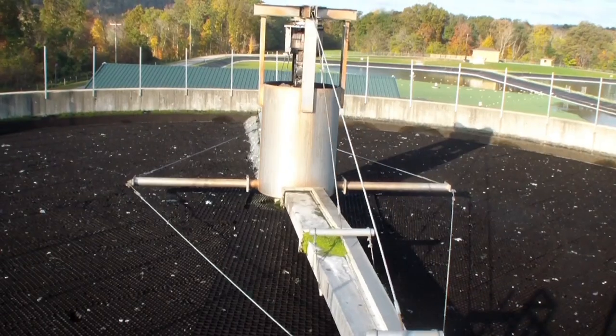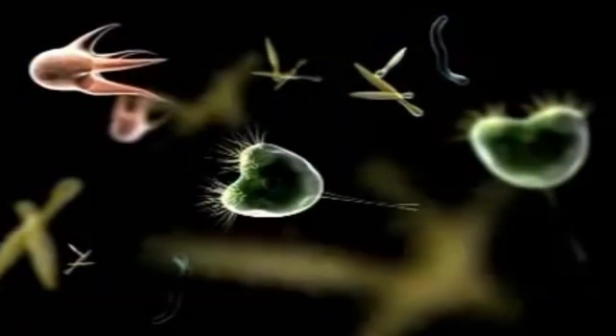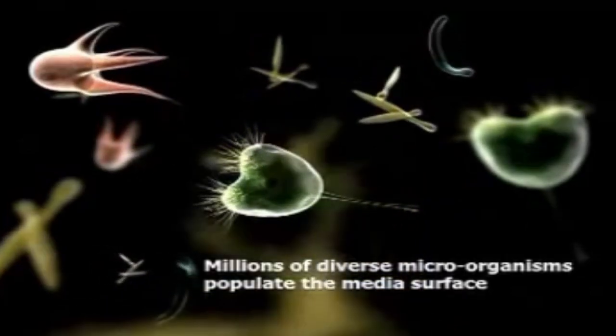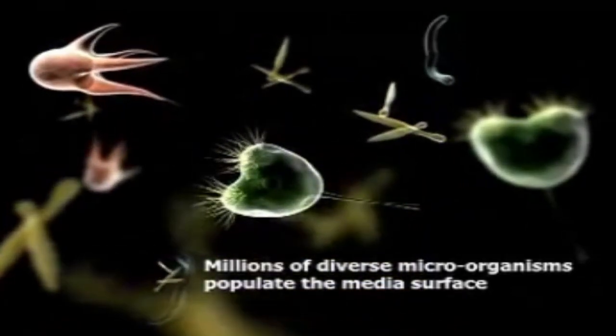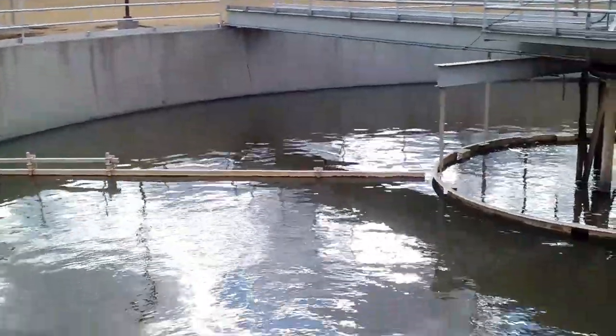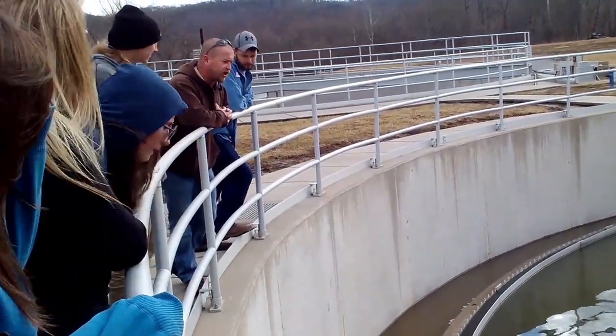After about two to three weeks, the water is pumped from the lagoons up to the bio towers, which are filled with a mesh of plastic covered in diverse microbes. The microbes eat bacteria and nutrients as the water filters down by gravity. The water then enters clarifier tanks, where any large particles that remain settle to the bottom and slowly decompose.